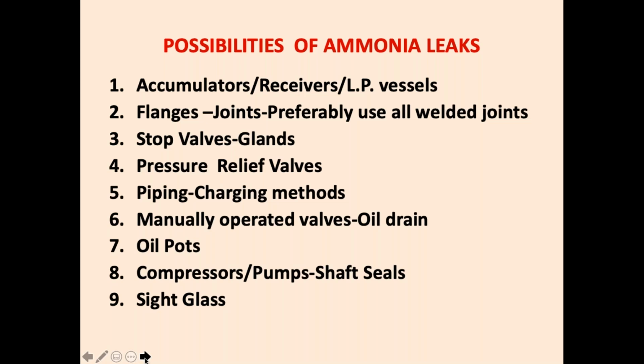Manually operated valves, especially oil drain, as we have discussed earlier, ammonia and oil are immiscible. If you don't use a good oil separator, the oil will be everywhere in the system: receiver, LP vessel, oil pot, drain, coil drain, and you need to drain the oil everywhere, because oil does not give any cooling and it can affect your cooling performance. So during oil draining, there is quite a chance of ammonia leak.